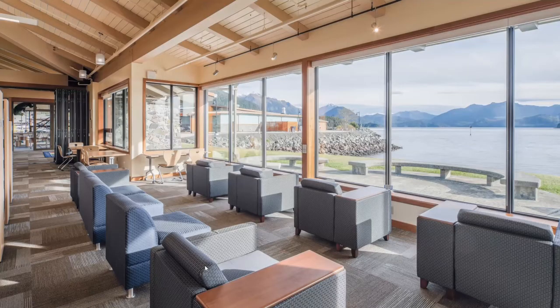This floor inside, we put in a radiant floor system throughout. It's only doing heating. We don't have a cooling load in this climate. Gorgeous view out here. Again, triple glazed windows. R20 on the outside of R15 inside of the metal stud wall. R60 roof. And the slab, we poured a topping slab on top of 4 inches of insulation. So it's very well insulated.